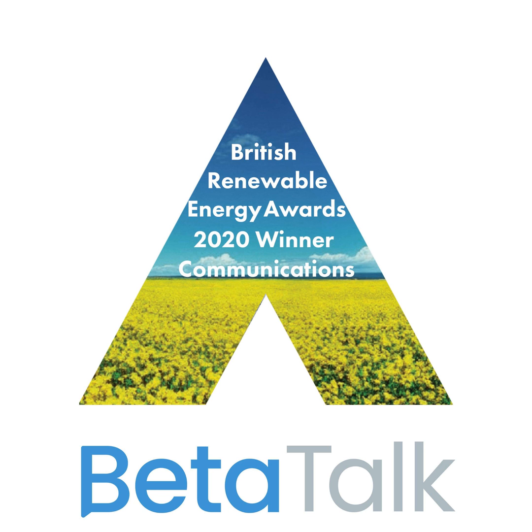The demand side response is really interesting for us, because essentially we're not bound by the same rules about how long you have to run the compressor. So we can ramp up and ramp down to zero, or to a very low rate, instantaneously. You can essentially treat it like an electric heater in that sense. You can ramp up to meet whatever demand, but you can also preload if you know that a cheap time or a beneficial tariff rate is coming up, and fluctuate the heat pump to do that. It's not part of what we do at the moment, but this project has let us explore that a little bit.